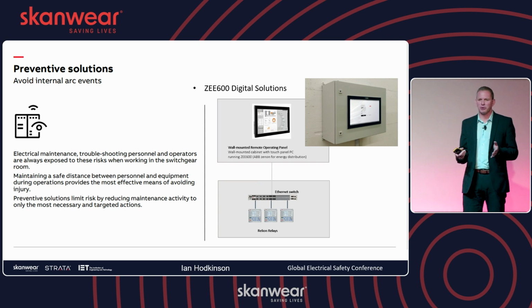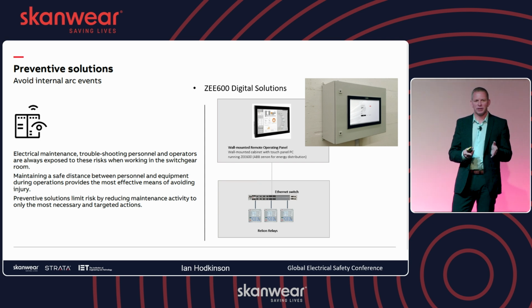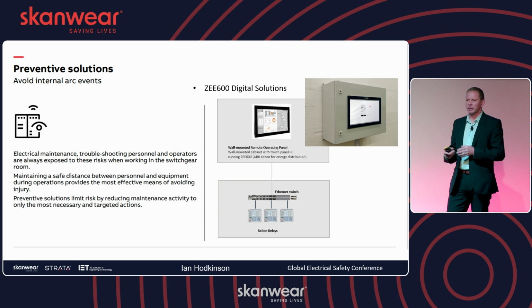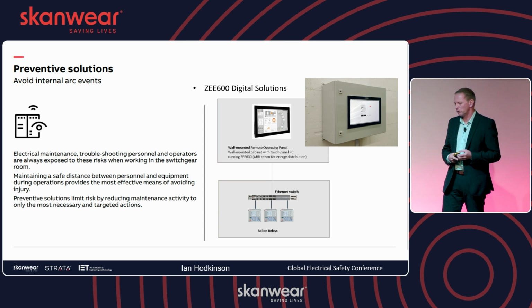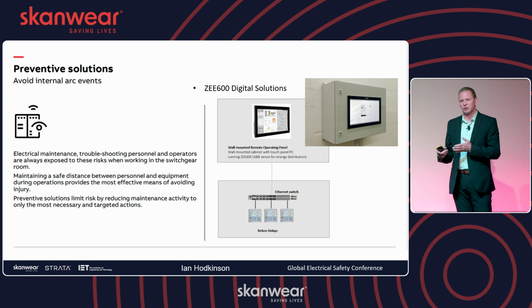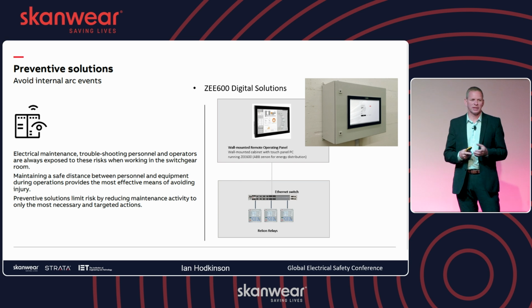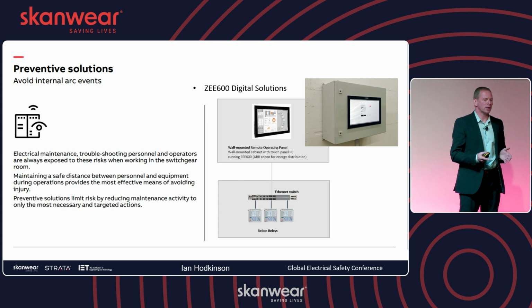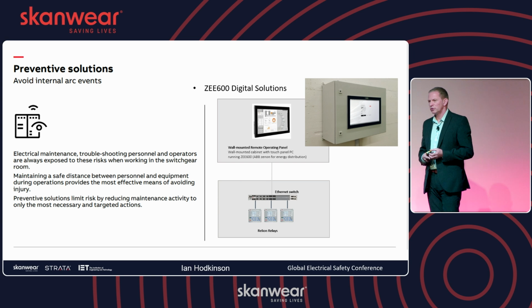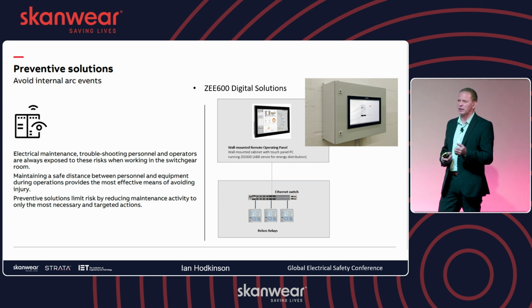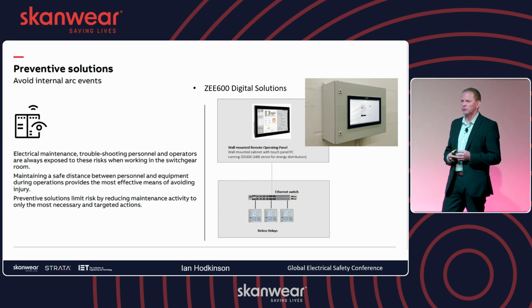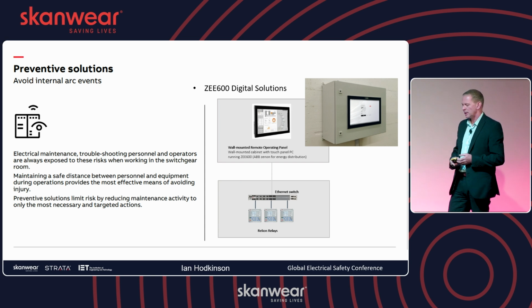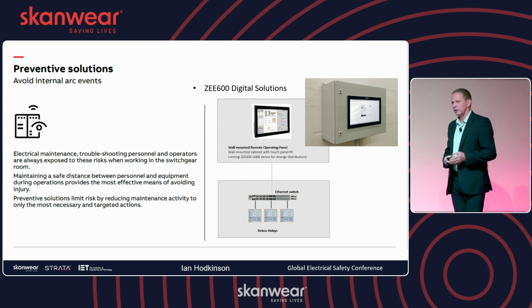This example is just a very simple remote operating panel: a touch panel PC in a cabinet, nicely wired up, with a simple communications cable connection from the switchboard and all the protection relays into the panel. You can see and visualize your full switchgear in a single line diagram on the screen. You can touch, zoom in, control, operate, see the events, take disturbance records, and change protection relay settings. But the most important thing is you're away from the switchboard, so this is a good preventative action.